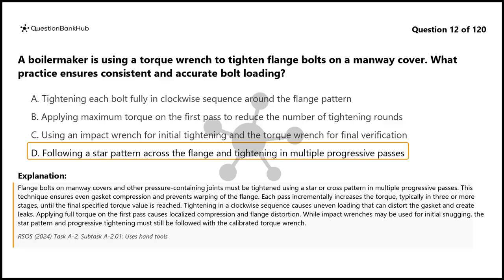Tightening in a clockwise sequence causes uneven loading that can distort the gasket and create leaks. Applying full torque on the first pass causes localized compression and flange distortion. While impact wrenches may be used for initial snugging, the star pattern and progressive tightening must still be followed with the calibrated torque wrench.